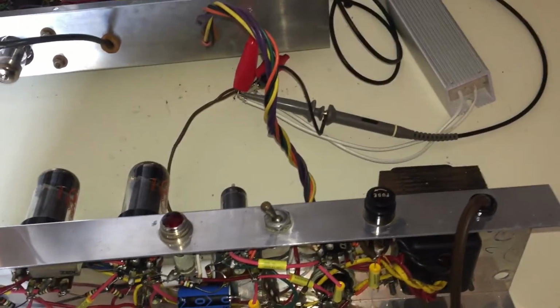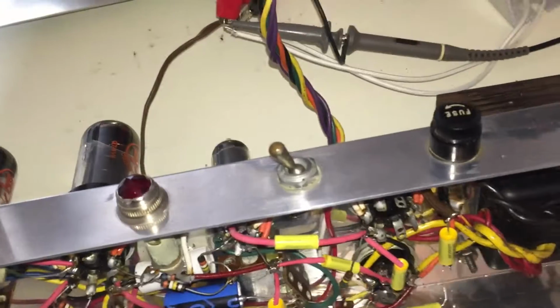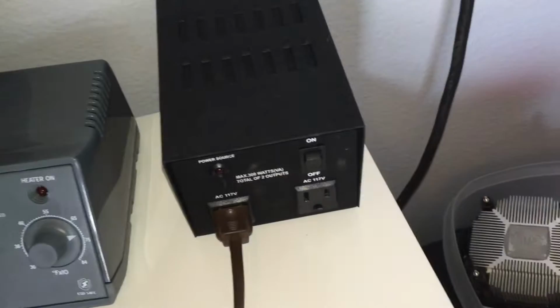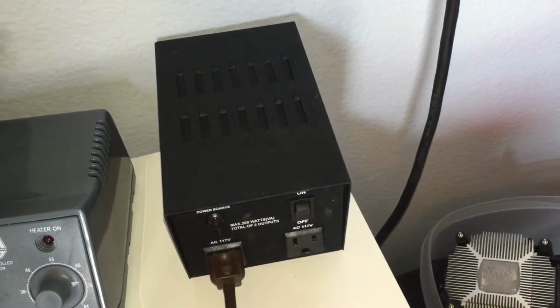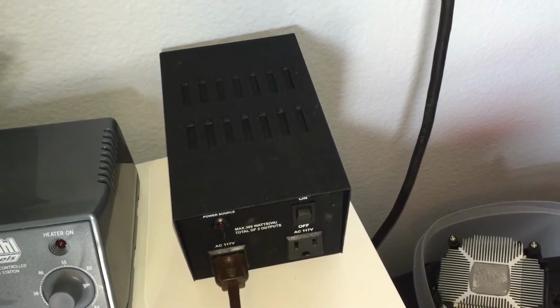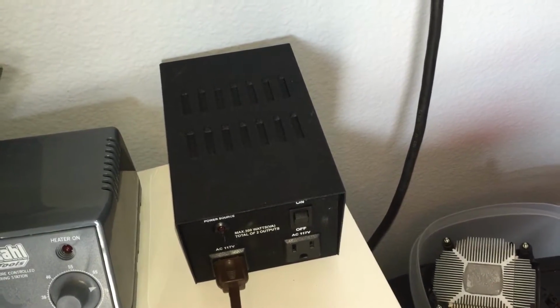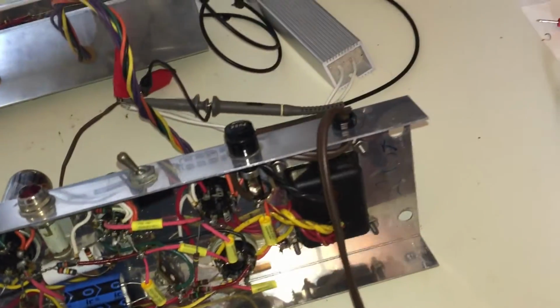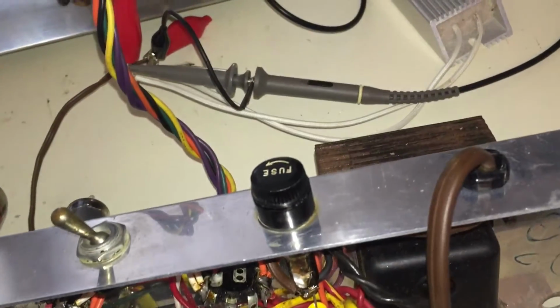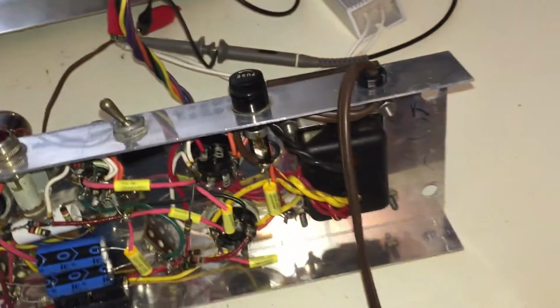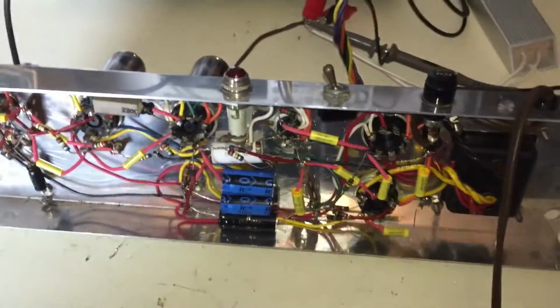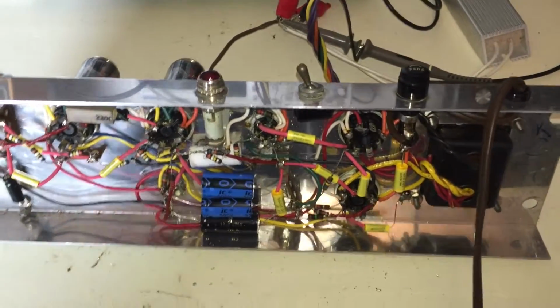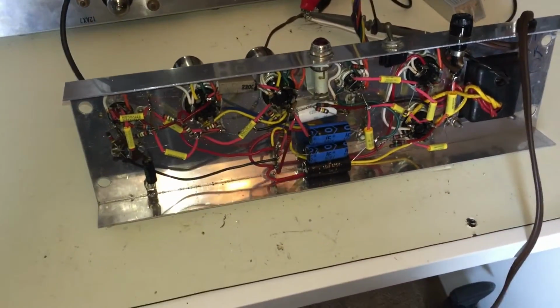I'll also note this is not directly connected to mains power. The power switch is plugged in, but it goes into an isolation transformer, so we'll be powering the unit from an isolated power transformer not directly connected to earth mains, as we should be doing. Some people use the light bulb method, but I have confidence in this approach. I do have a fuse in line, I'm not touching the chassis when I turn it on, and the chassis is physically disconnected from earth — it's floating, with no reference.